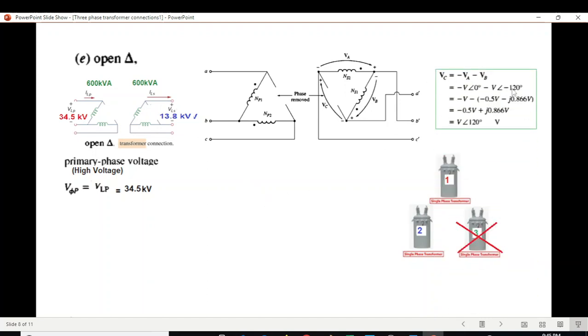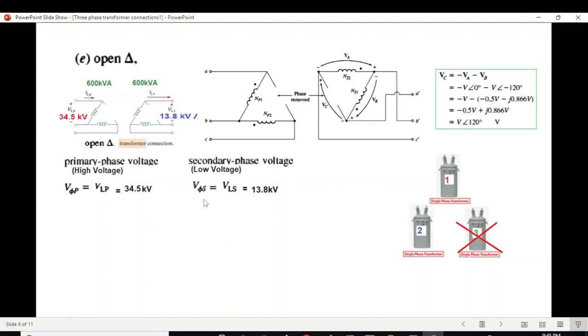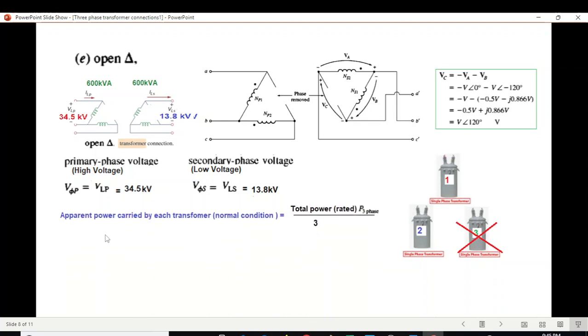Even though one terminal is open, a calculation in the book shows that the open-side voltage Vc has the same magnitude as Va and Vb. Therefore, the secondary phase voltage equals the line voltage of 13.8 kV. In normal conditions, each transformer carries total power divided by 3 — one-third of the total power.